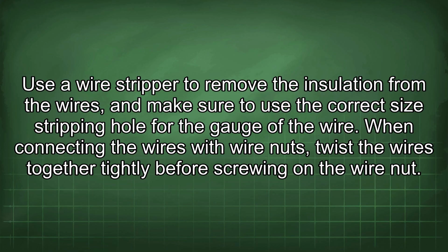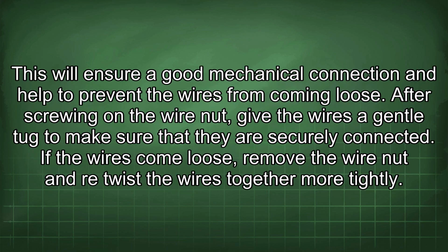When connecting the wires with wire nuts, twist the wires together tightly before screwing on the wire nut. This will ensure a good mechanical connection and help to prevent the wires from coming loose. After screwing on the wire nut, give the wires a gentle tug to make sure that they are securely connected. If the wires come loose, remove the wire nut and retwist the wires together more tightly.